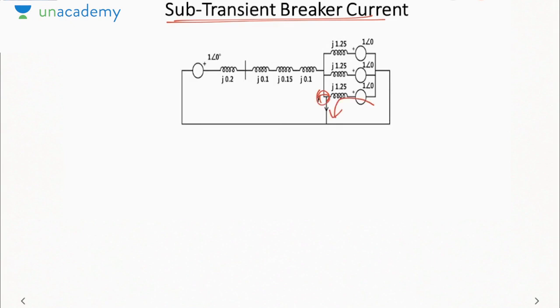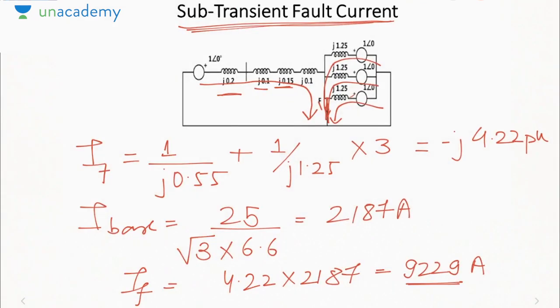Now this current will go directly into the fault. This current will go like this. This will go like this. This will go like this. So three currents will have to pass through the circuit breaker to go into the fault. But for the motor at which the fault is occurring, the current will directly go into the fault, because for that motor the breaker lies after the fault. Okay. What I am saying is, I will show you in this figure.